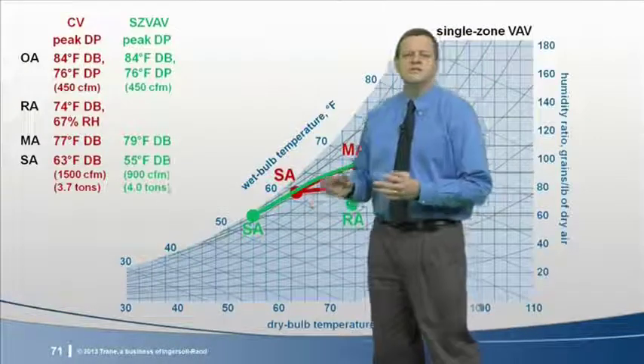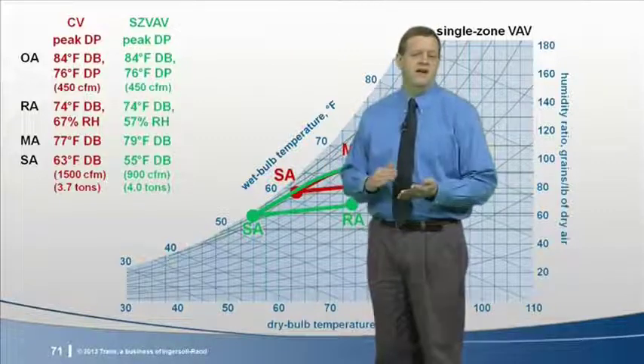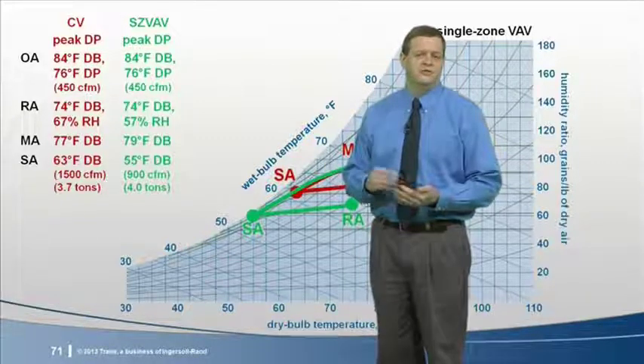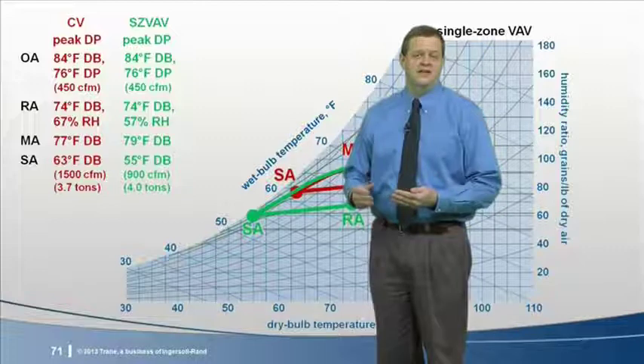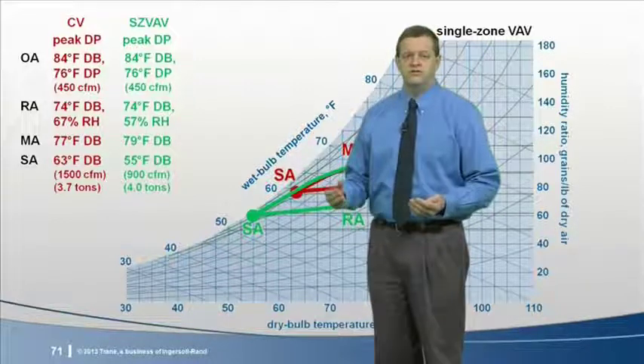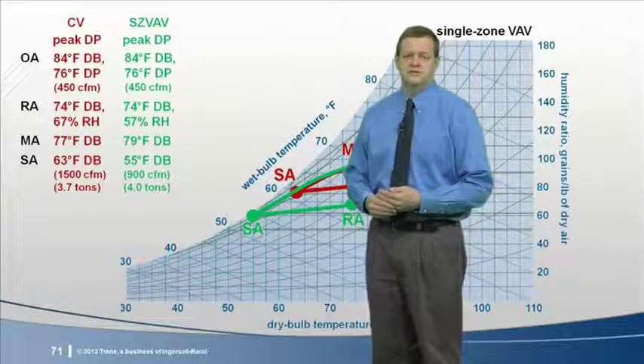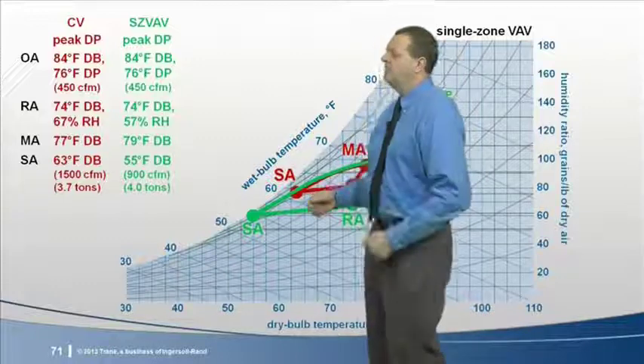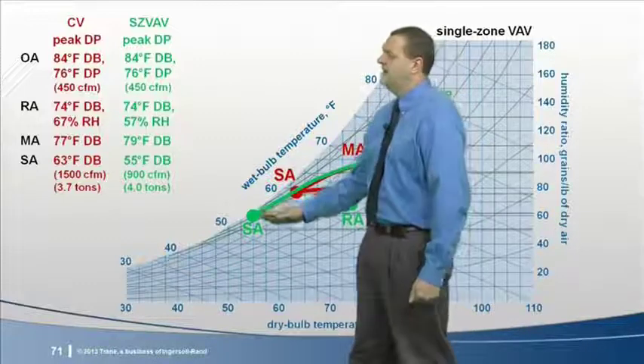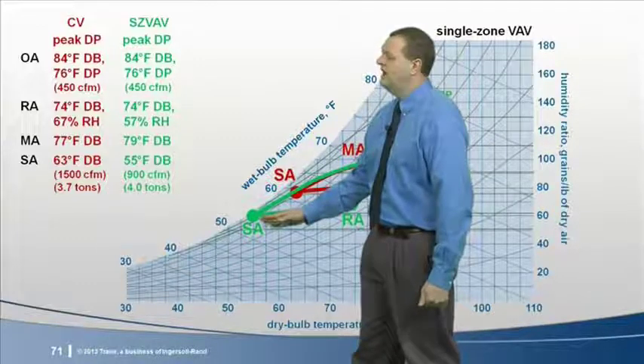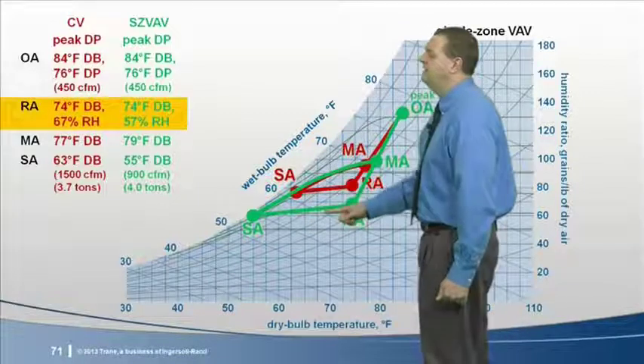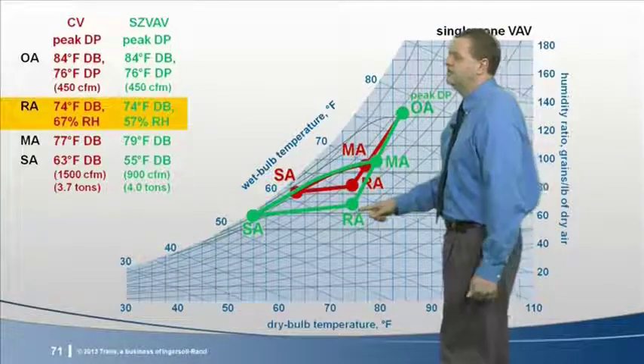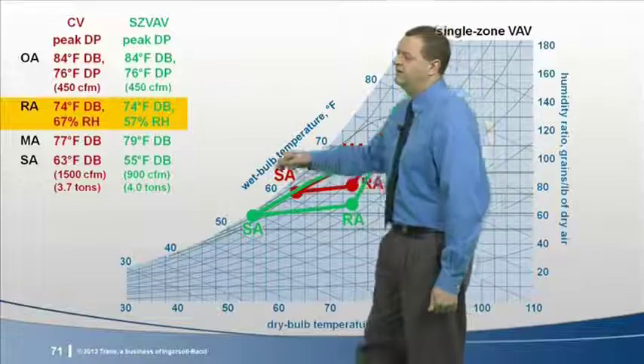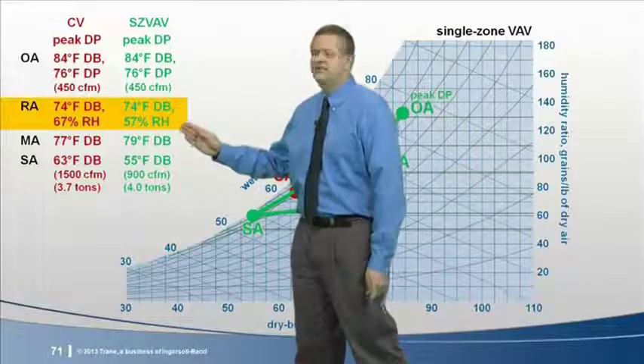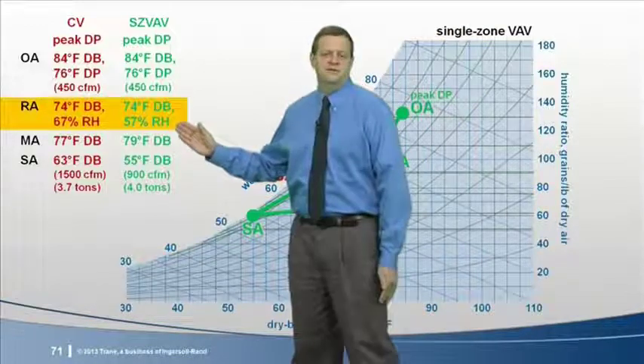Reducing the airflow allows the system to continue supplying the air at a cool temperature, which means it's also dry. The coil removes more moisture, improving dehumidification performance. At this part load condition, because the supply air is still cool and dry, the relative humidity in the classroom rises to only 57% with the variable speed fan compared to 67% with the constant speed fan.